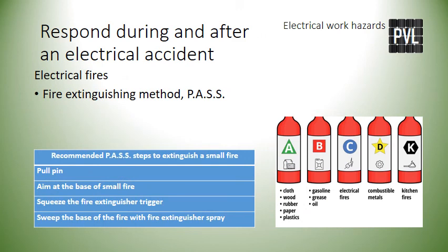Electrical fires are dangerous because often plastics and metals are set ablaze, releasing toxic fumes and potentially causing severe burns or asphyxiation. Electrical fires can be more difficult to extinguish than ordinary combustible fires. First, call for help. If the fire is small or contained, attempt to put it out with a class C fire extinguisher. If the fire gets out of control, evacuate the area immediately and help others do the same. It is recommended that electrical workers be trained in using different types of portable fire extinguishers. The basic method to use a common portable fire extinguisher is the PASS method: pull, aim, squeeze, and sweep.